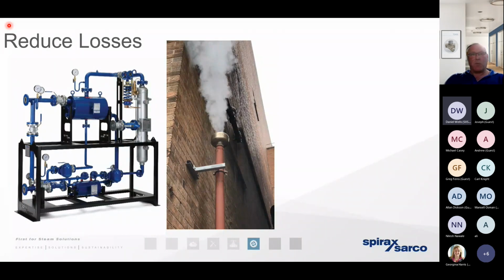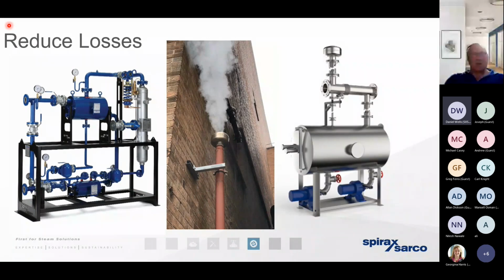But even if we can't, even if we've got nowhere where we can use the energy that's contained within that flash steam, if we can at least just condense it, or condense as much of it as we possibly can, we're still providing that expansion brake. It just means that by condensing as much of the flash steam as we possibly can, we're increasing the mass of condensate that we can get back to the boiler house. And if we're increasing the mass of hot water that can be diverted back to the boiler house, then of course we're reducing the amount of energy that we need to raise steam again.